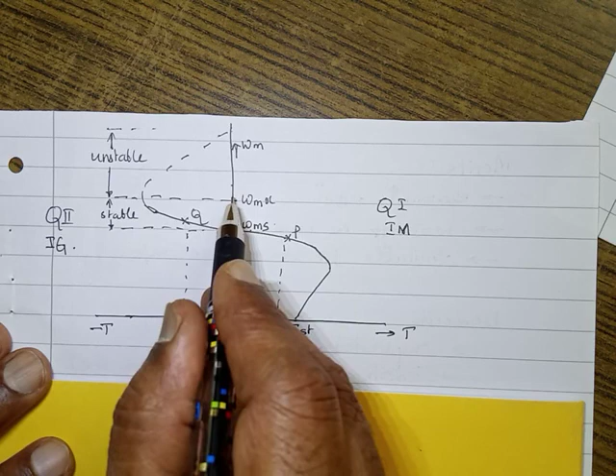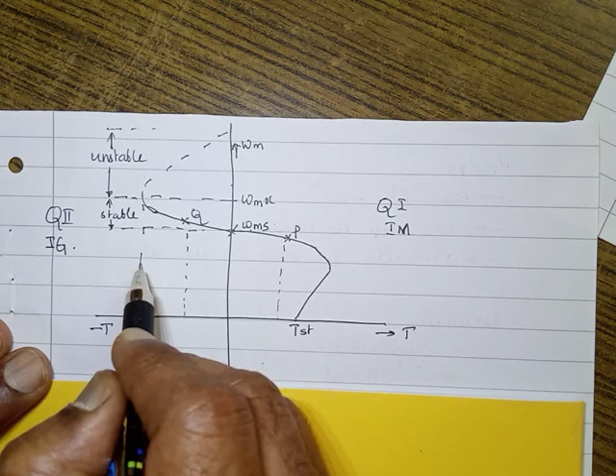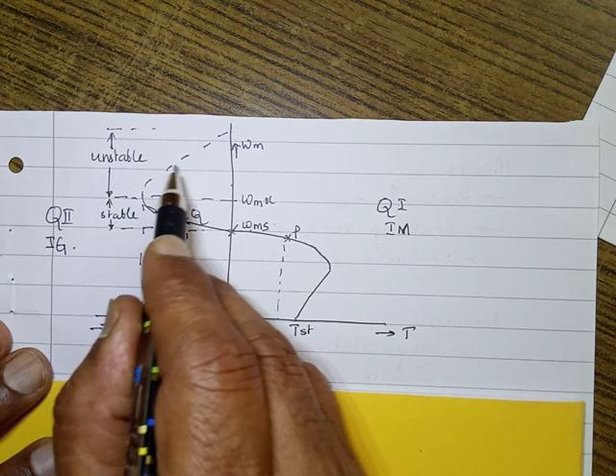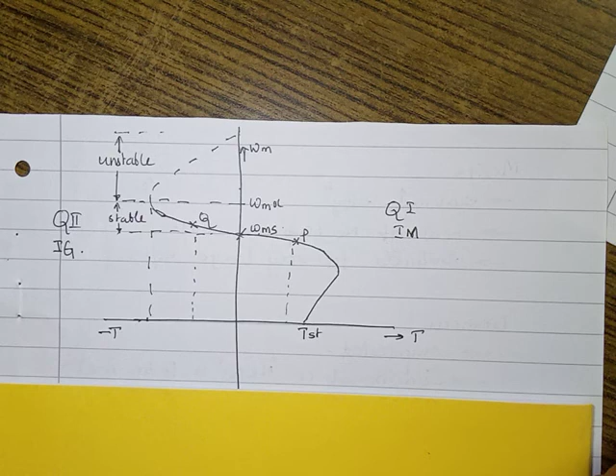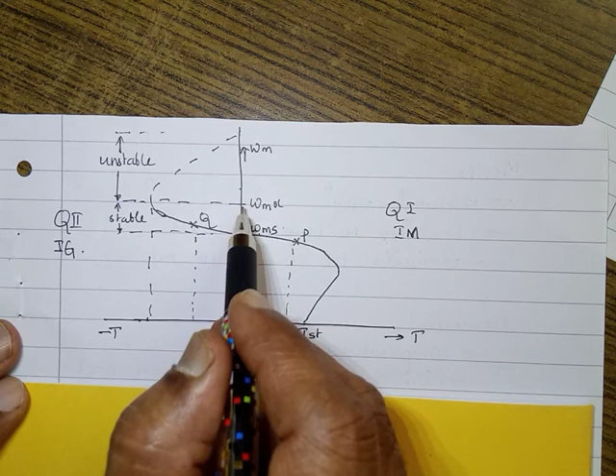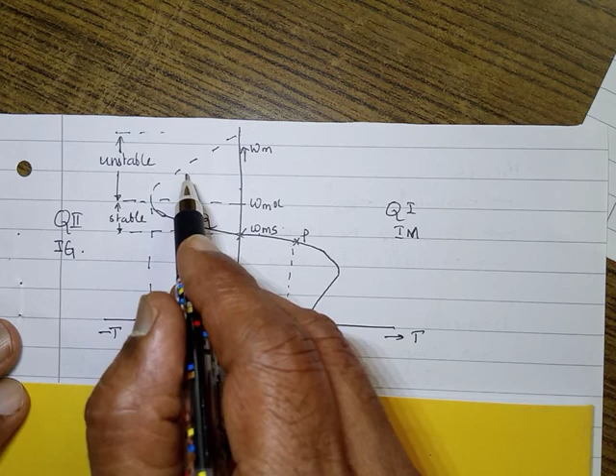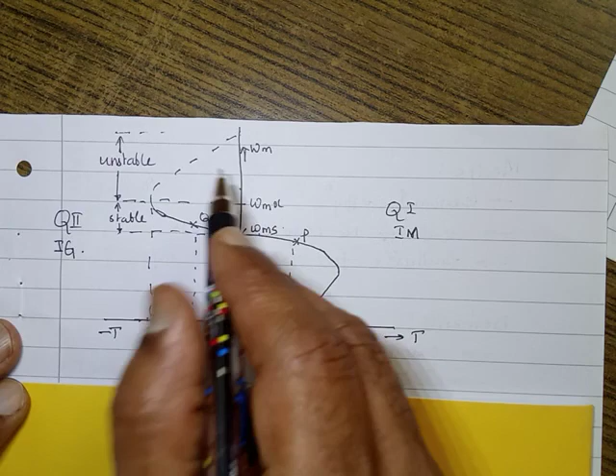This torque increases as the speed increases and reaches a maximum. This is the maximum braking torque. After that, as the speed still increases, the braking torque decreases. So look at that a little carefully. As the speed increases, the braking torque increases, the opposition becomes more. Hence, that is the stable operation. But when the speed becomes more, if the braking torque becomes less, then obviously the speed again becomes more. We lose the control. That is why this portion is unstable.